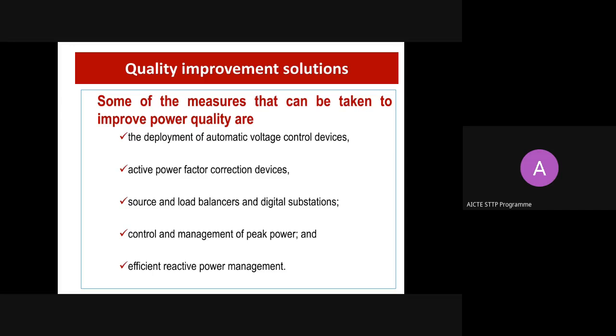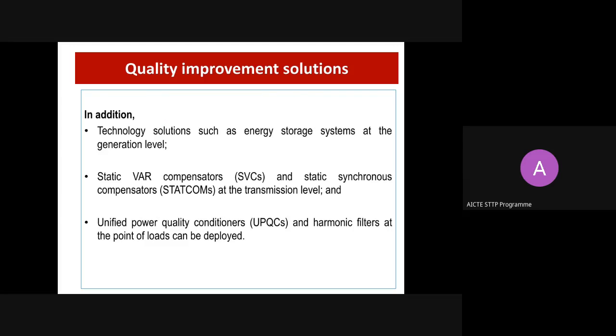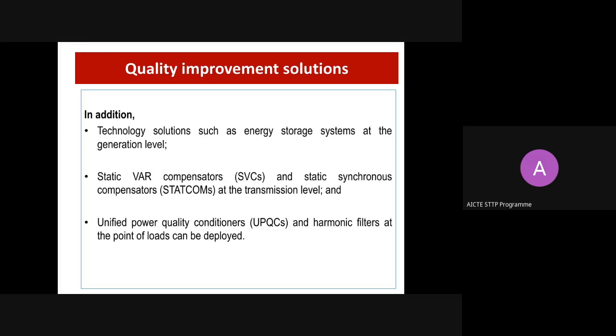And then we are going for digital substations, control and management of peak power, and efficient reactive power management. These are some of the things we are doing in the current day system to maintain or improve the quality. With additional technology-based systems, we are now thinking of static VAR compensators and static synchronous compensators at the transmission level, and unified power quality conditioners and harmonic filters at the point of loads. We are improving the quality by using SVC and STATCOM at the transmission level, and UPQC and harmonic filters at the distribution level, at the consumer premises.